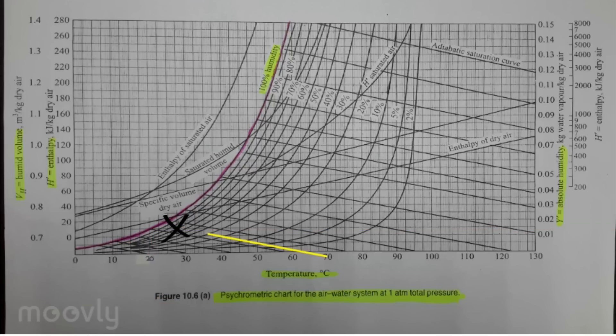Draw a constant wet bulb line from point A to the 100% humidity line to obtain the wet bulb temperature of moist air, which is around 22.5 degrees Celsius.